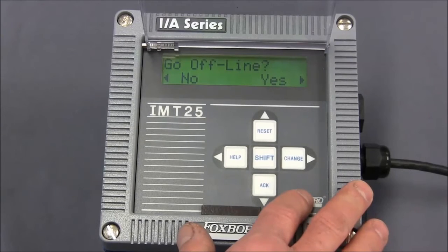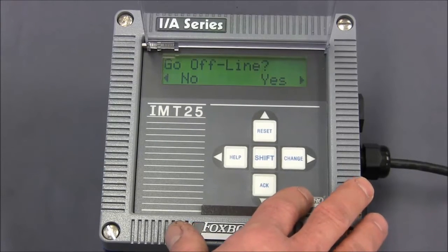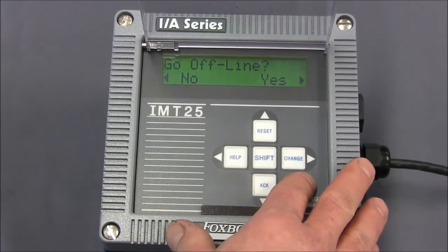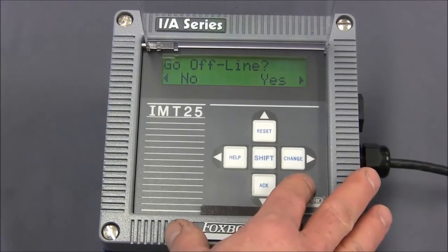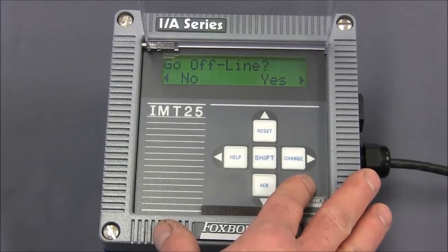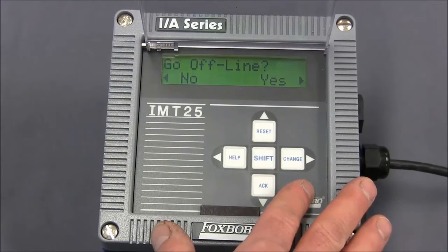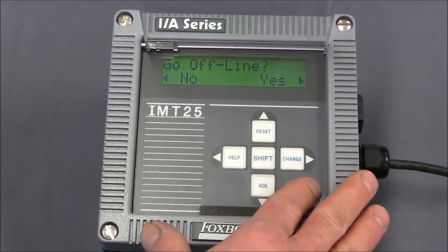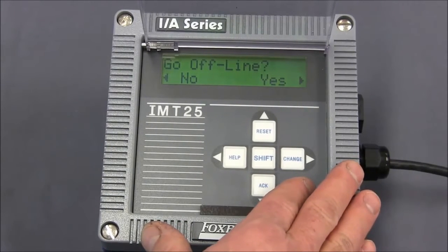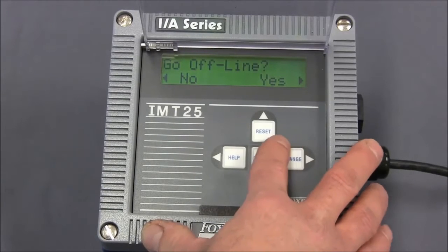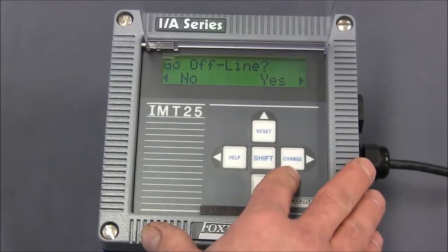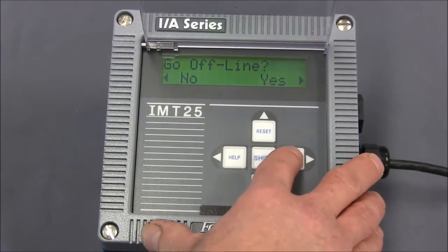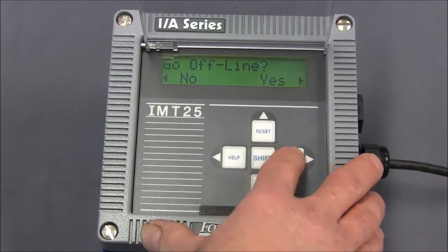When you do that correctly the first time, it'll say go offline. What that means is if you're in a control loop, the control loop should be switched into manual before you continue. Because now, once we say yes, the transmitter will output four milliamps regardless of the flow value. So we're going to hit the right arrow key or the change key to say yes, it's okay to go offline.